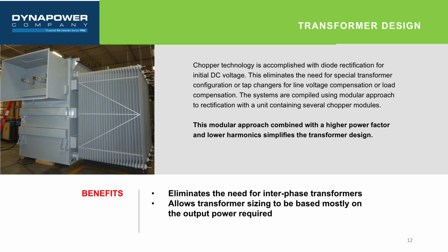Choppers require a lower kVA for the same output power, so transformer sizing is mostly based on output power requirements. Transition can be made from a high voltage line down to the required AC input for the chopper with a single transformer, in which each chopper section provides independent current control of each secondary.